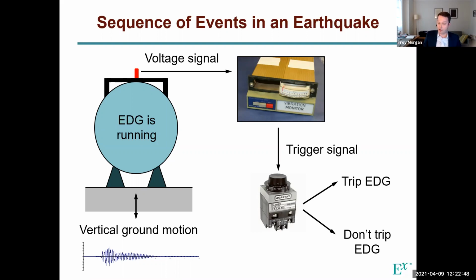That relay takes the signal and turns it into a binary yes/no output: either trip the generator off, shutting it down, or don't. This is a problem clearly, because shutting the generator off would then limit the amount of power available to the cooling systems.